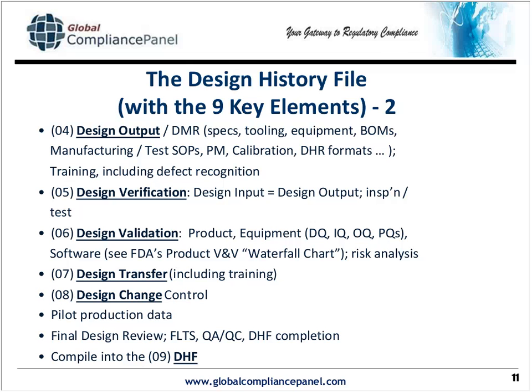These are the various, I use the term verification in the terms of inspection, test, checklists, etc. So here again, you're making sure that every design input requirement has been met by a document, a design output document, and or testing, whatever is necessary to prove that your inputs have been addressed.